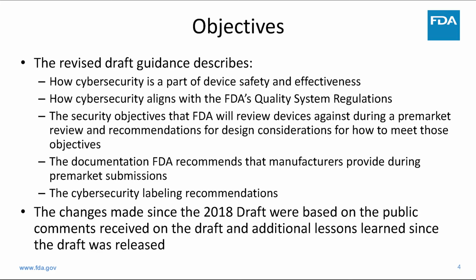Again, it does a crosswalk with the QSR, the quality system regulations, and it speaks to how devices will undergo their pre-market review, considering those design aspects. We put a lot of detail, a lot of focus in the documentation that's necessary, that's recommended for manufacturers during pre-market. There's a whole section on labeling, and that we'll get into in terms of the software bill of materials as well.